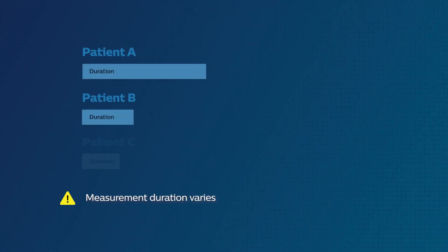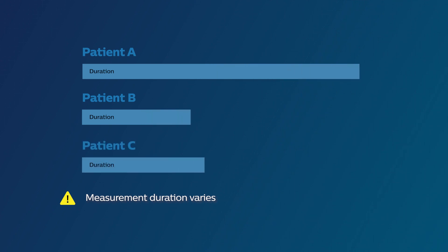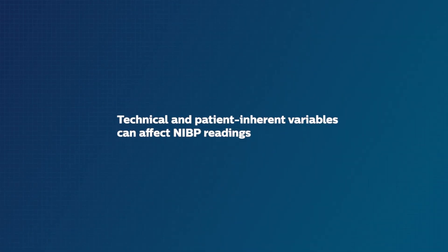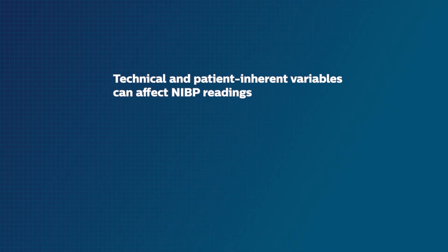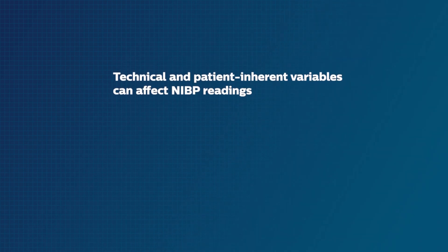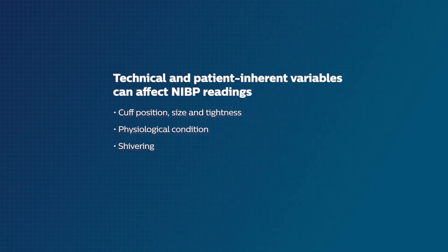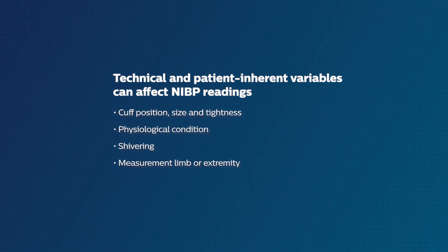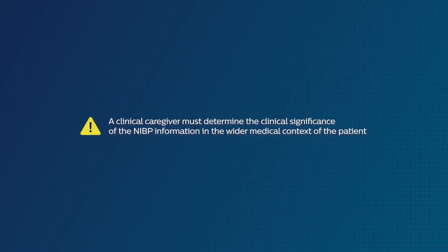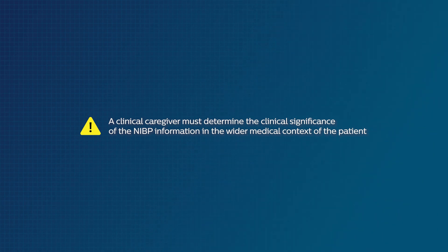Measurement duration varies based on patient and measurement conditions. NIBP readings can be affected by technical variables such as the position of the cuff in relation to heart level and cuff size and tightness, as well as patient inherent variables such as physiological condition, shivering, the measurement limb or extremity, and physical exercise. Therefore, a clinical caregiver must determine the clinical significance of the NIBP information in the wider medical context of the patient.